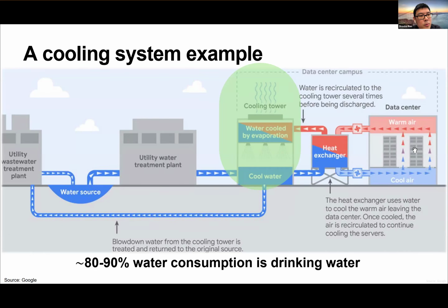This heat will be circulated through a closed loop to a heat exchanger. This closed loop circulation can be either using air, or sometimes for AI servers, especially for training, they will be using direct-to-chip cooling. Basically, they use a closed loop to transfer some liquid to the servers inside and then move the heat to the heat exchanger. Or sometimes they put the entire server into some liquid, a special non-conductive liquid. That's called immersion cooling.